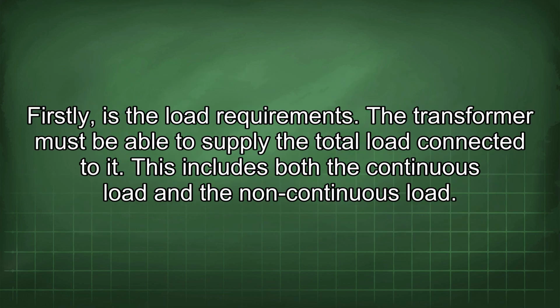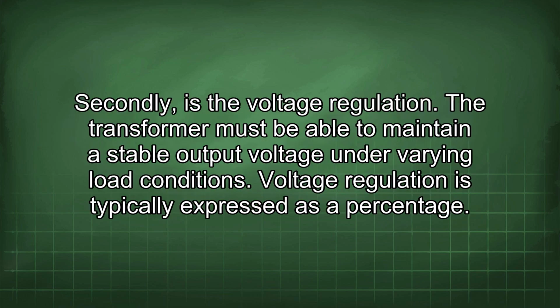Firstly is the load requirements. The transformer must be able to supply the total load connected to it. This includes both the continuous load and the non-continuous load. Secondly is the voltage regulation. The transformer must be able to maintain a stable output voltage under varying load conditions. Voltage regulation is typically expressed as a percentage.